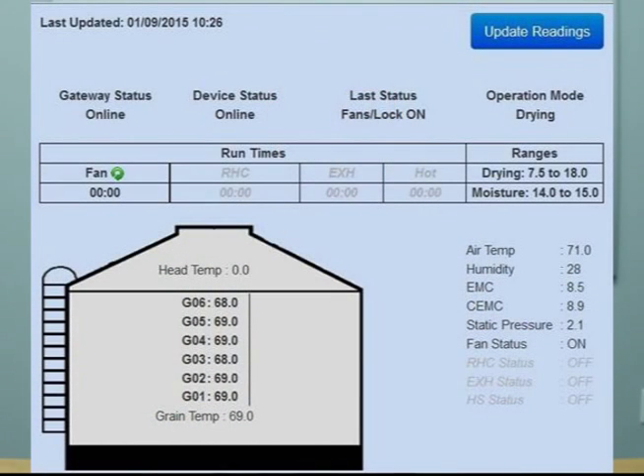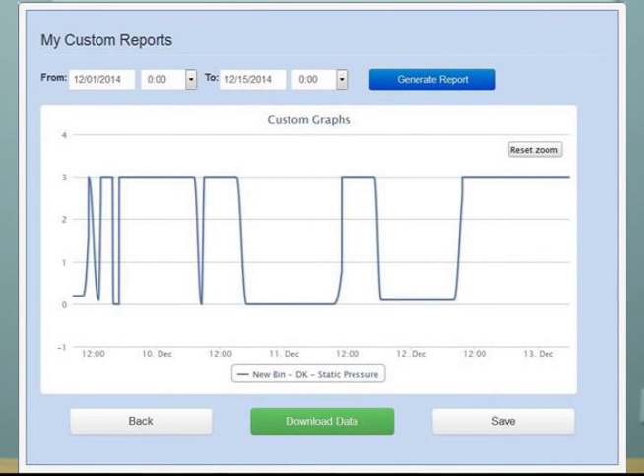On the two screens shown, the static pressure is displayed along with the fan status so you know what that pressure is and can confirm the fans are running. The graph shows the static pressure gauge operating in relation to when the fans are on — it goes to zero when the fans are off and shows the static pressure reading when the fans are running.